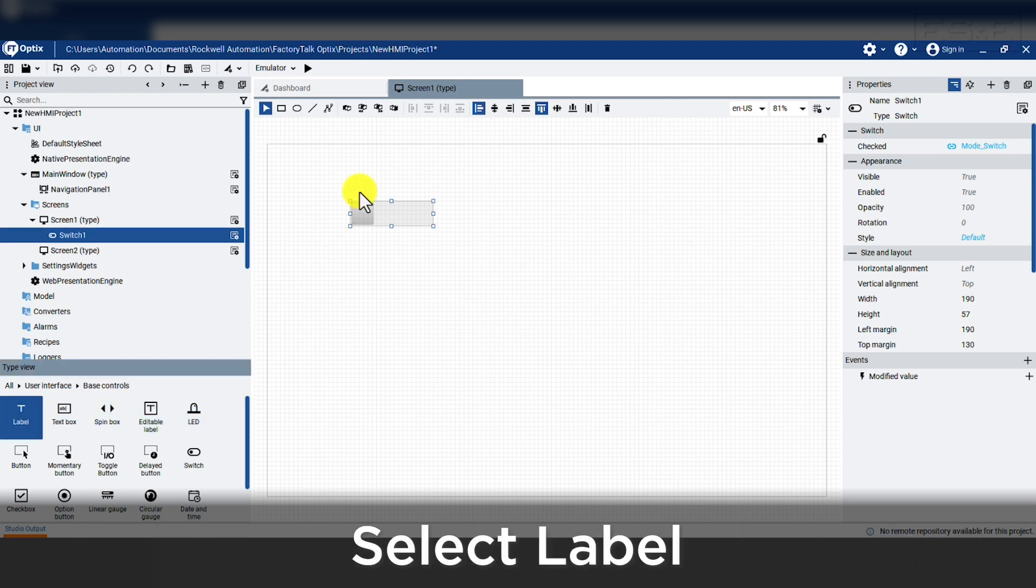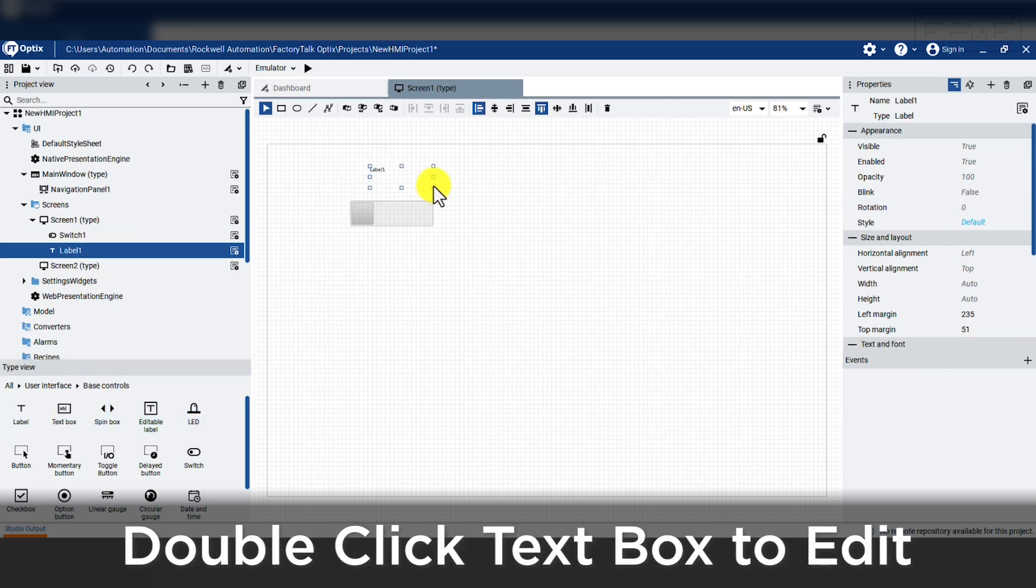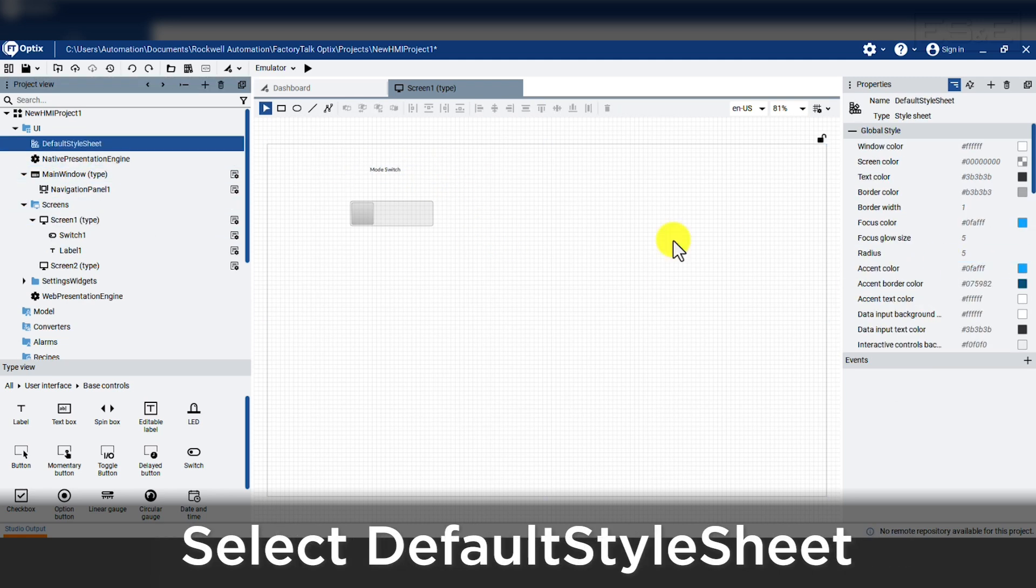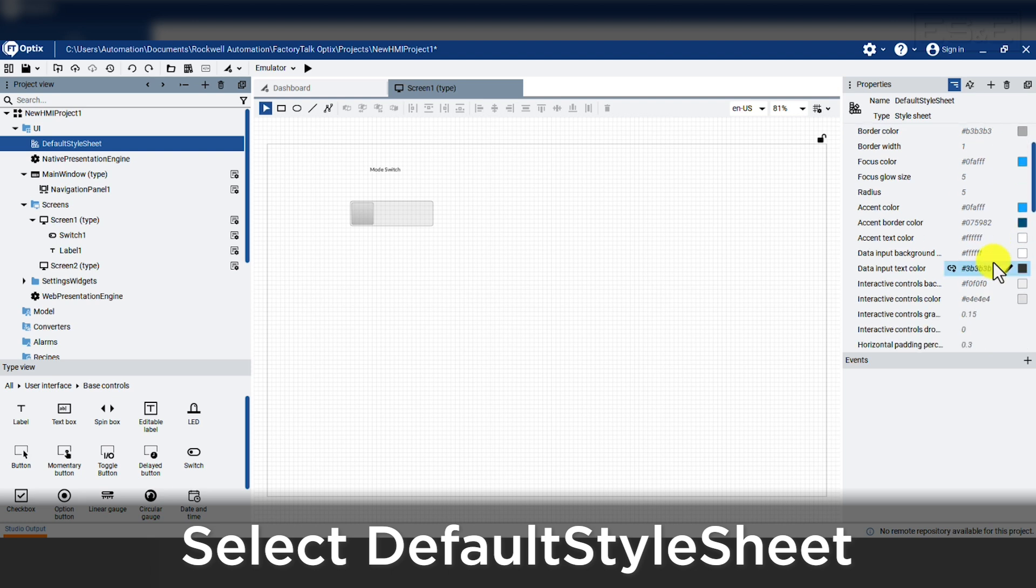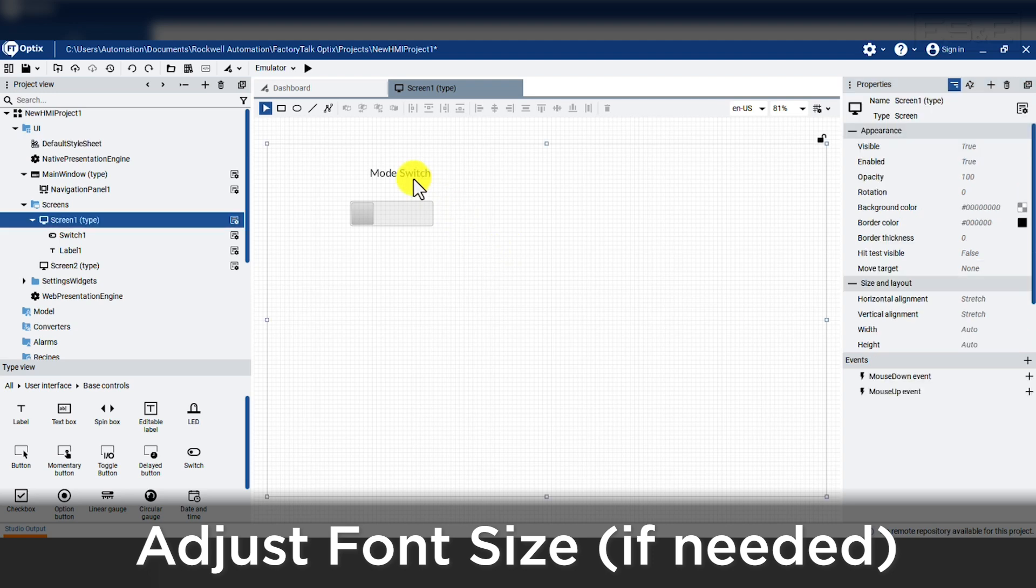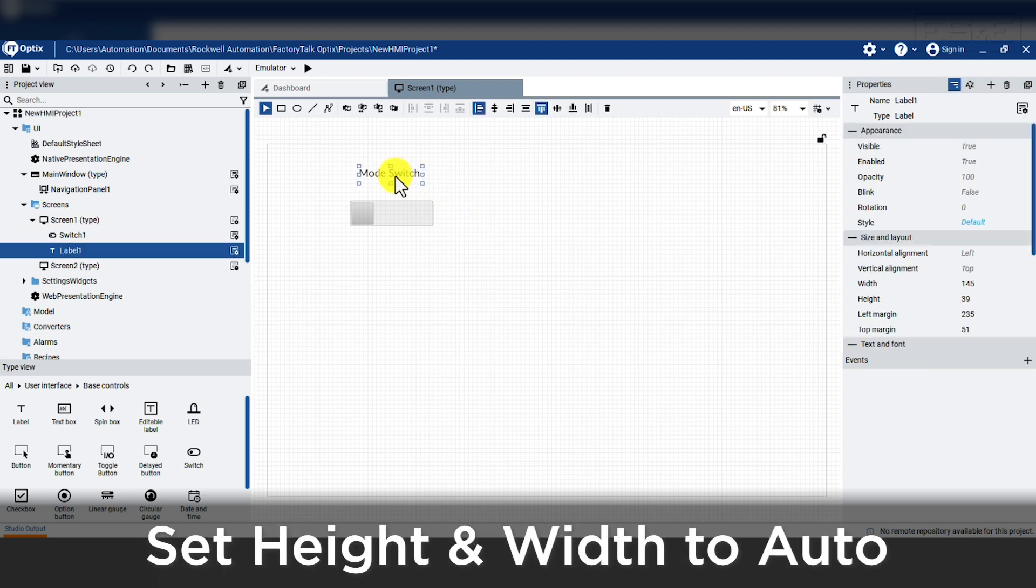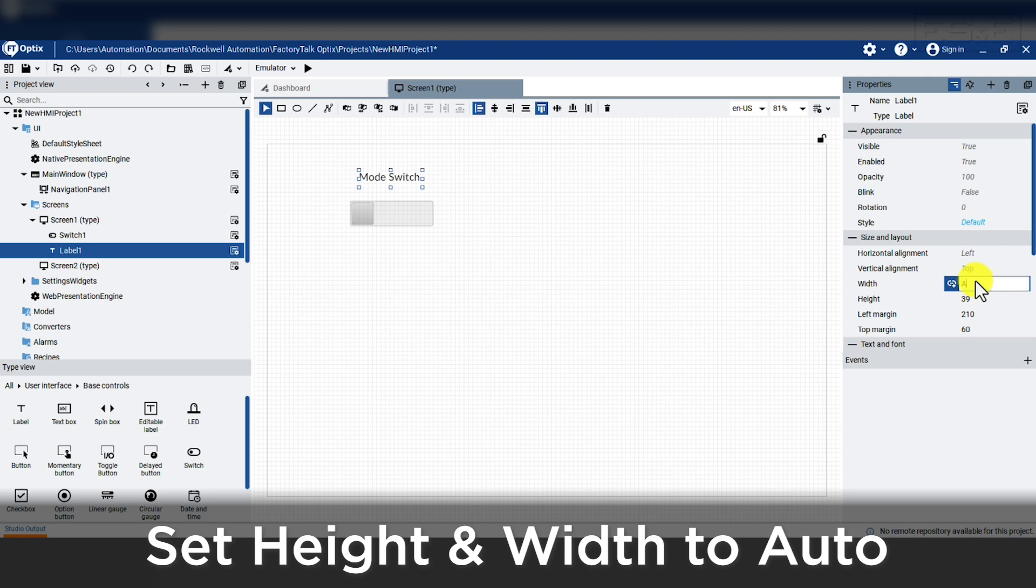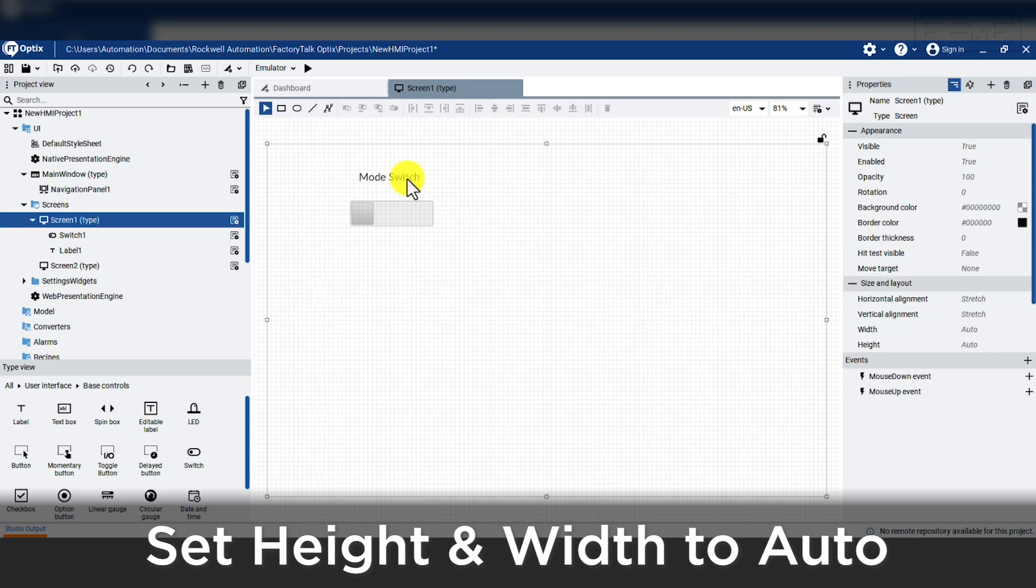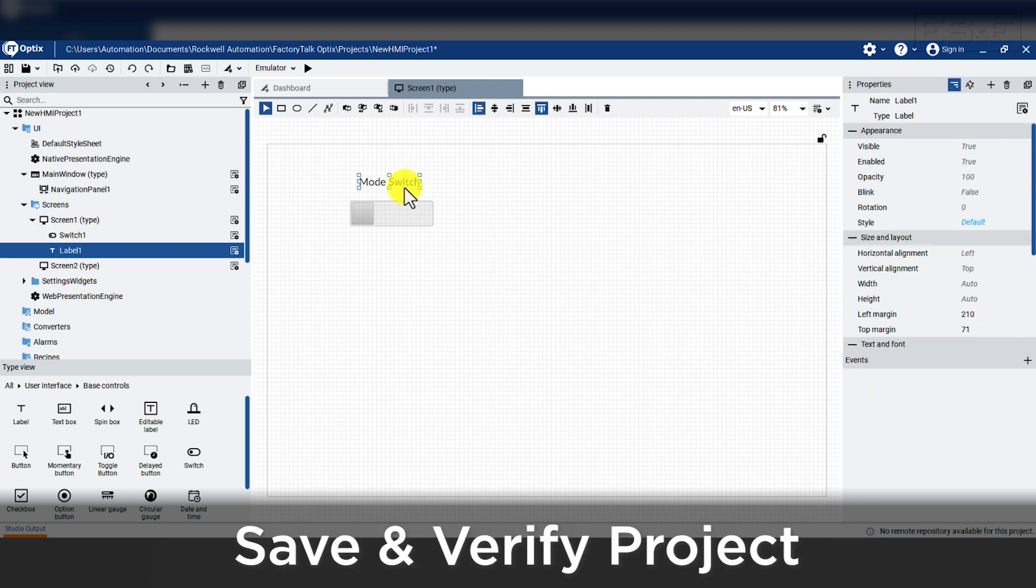We can then add a text box to label the switch. We double click in the text field and type in mode switch. But then we can also move to the default style sheet and increase the font size from 12 to 24. We will see our text will automatically update. We will also want to verify that the width and height are set to auto. If you see a value in these properties, you can simply edit the number and type in the word auto. This will fit the box to the text typed into the box. Now we have finished adding objects to the screen so we should save our project.